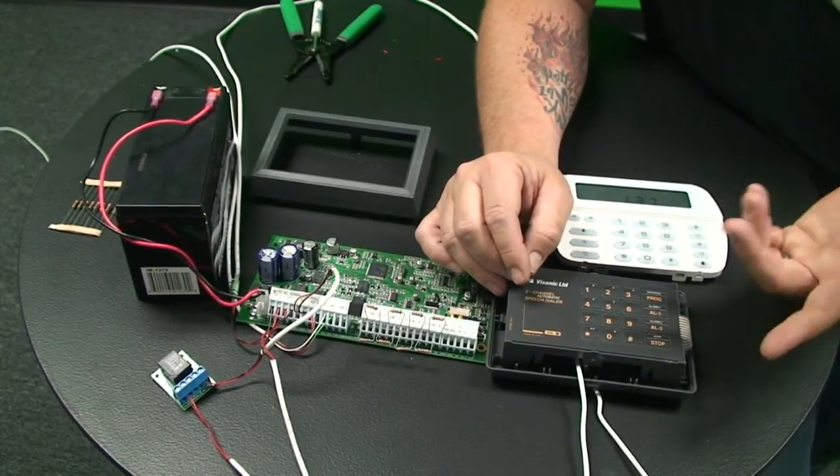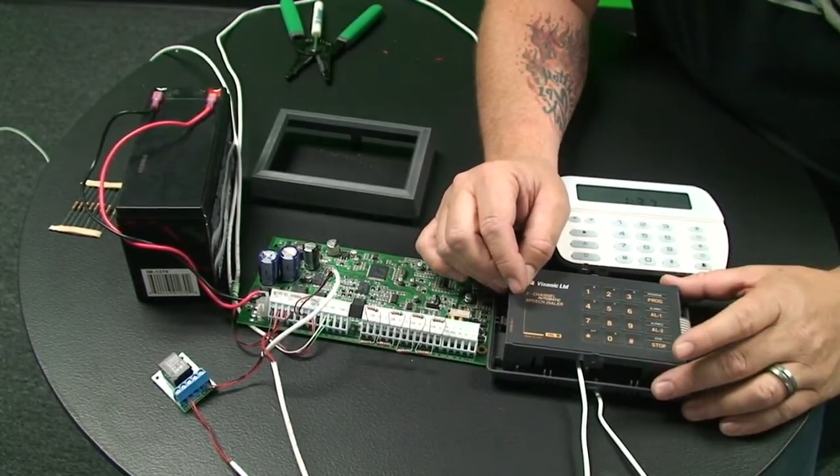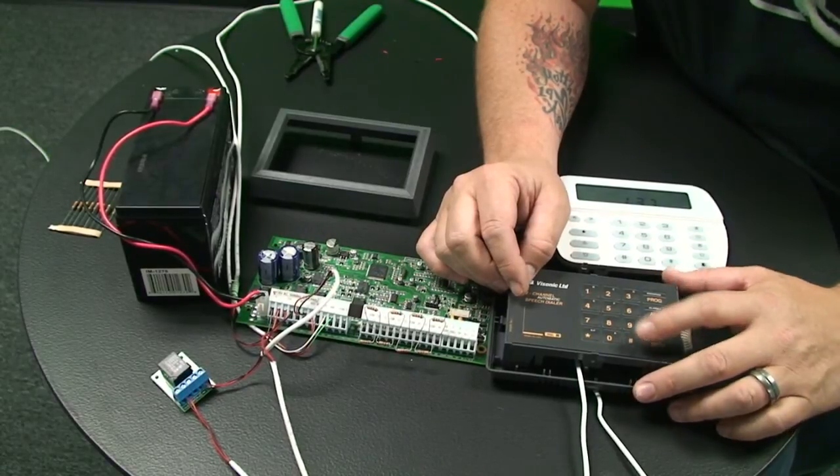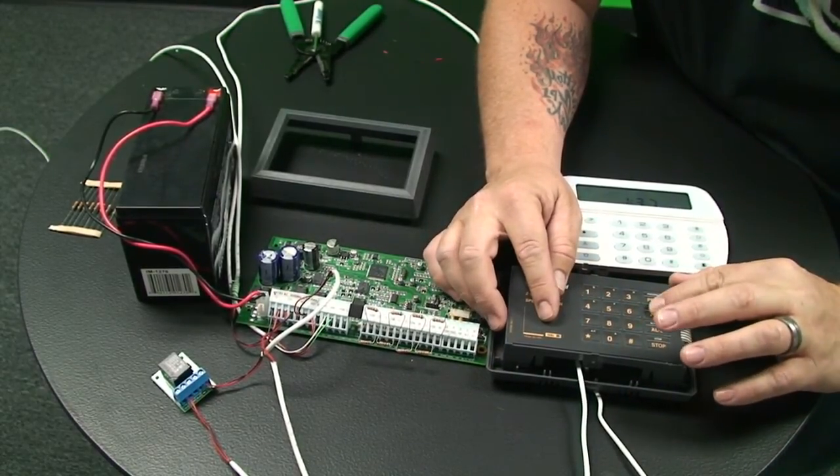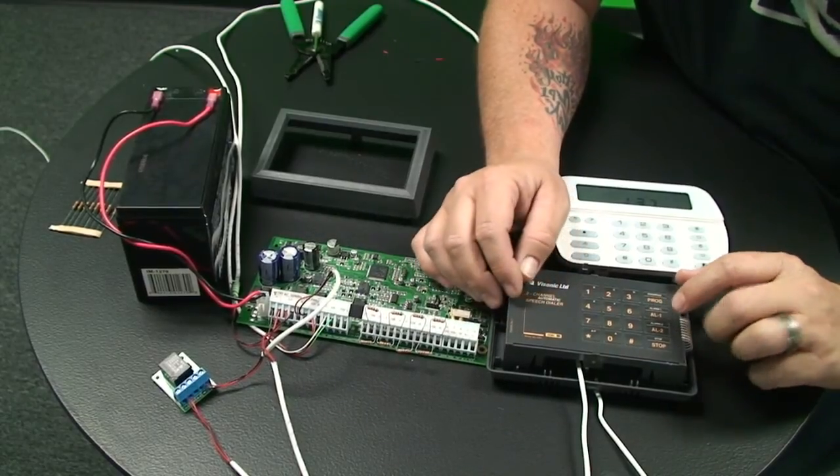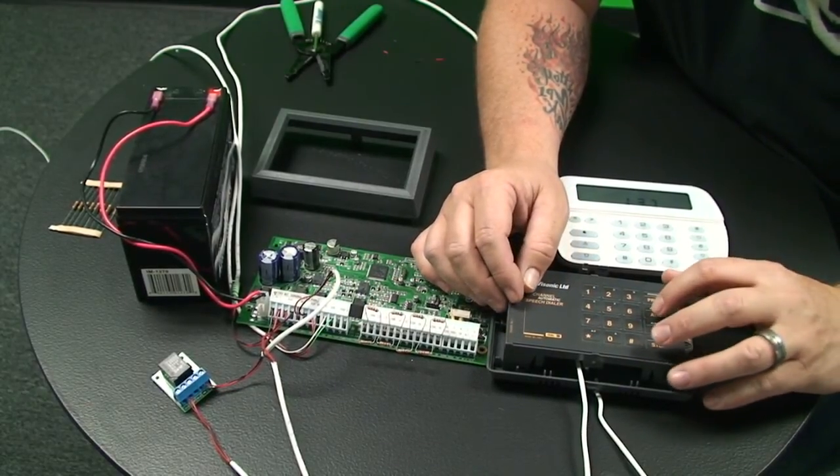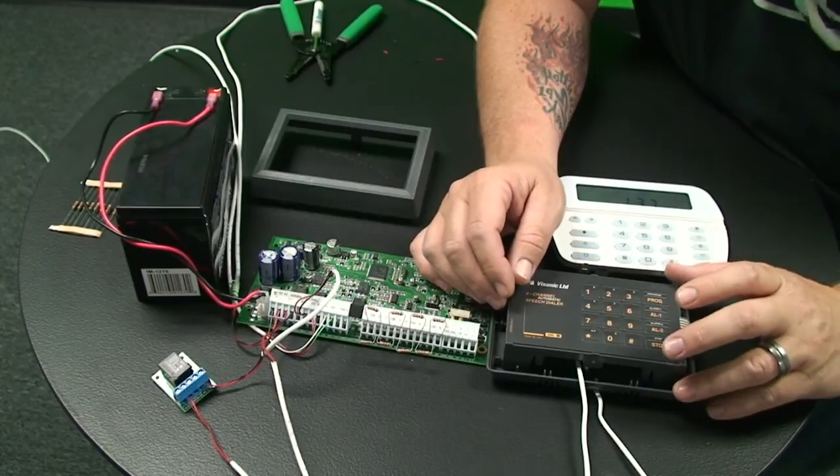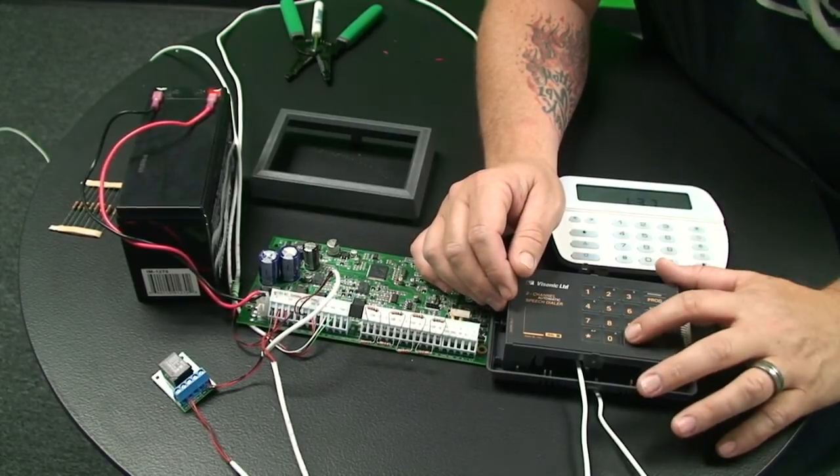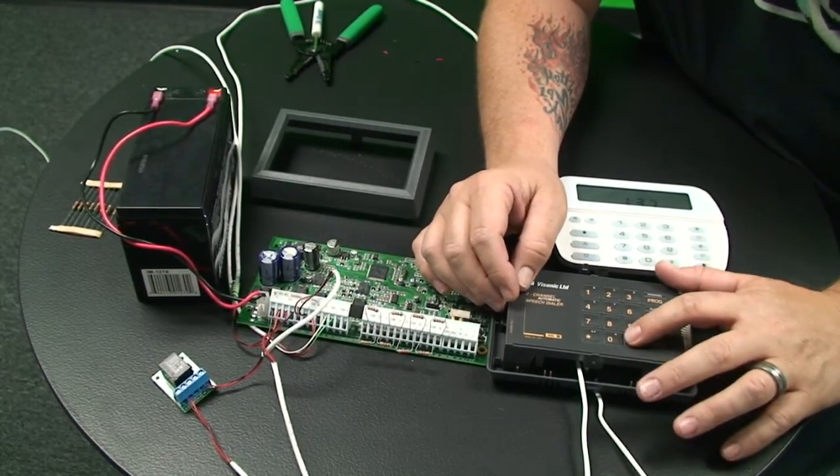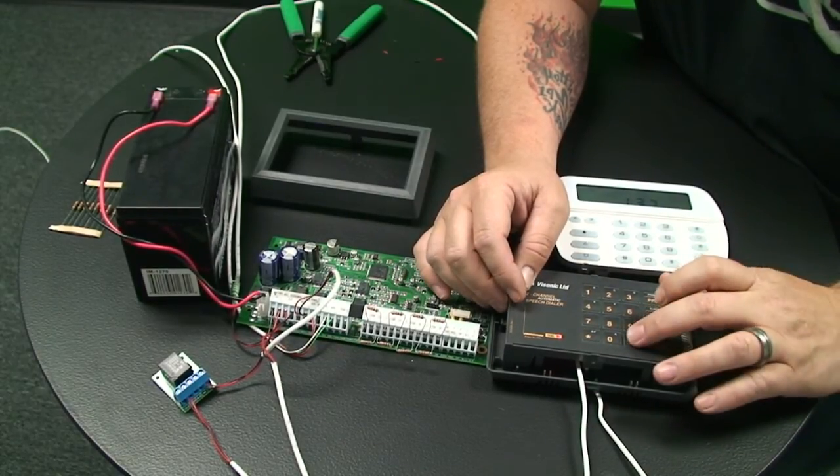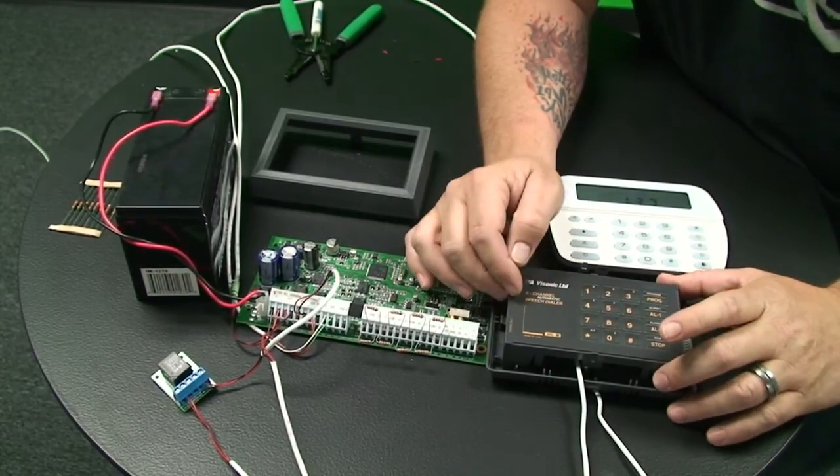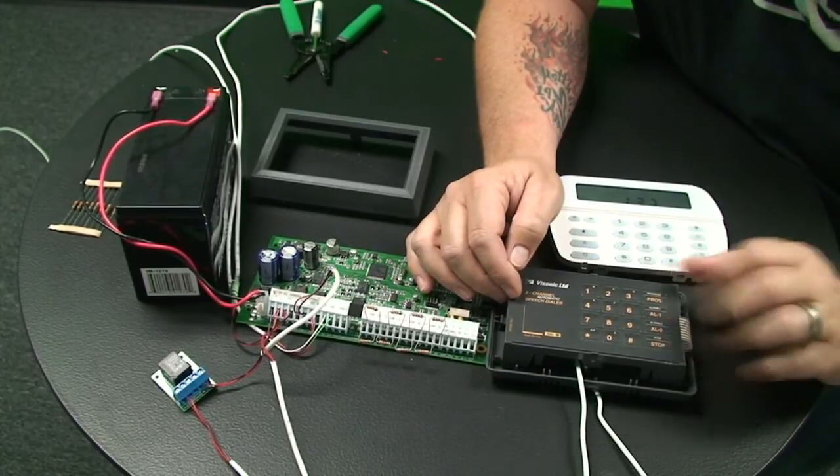So now we can actually program a message, and this is very simple to do. You can press the pound key, and then you'll see the dial light come on. Immediately press and hold down AL1. When you do that, you can actually deliver your message, and you have about 10 seconds to deliver a message. When you're done, you just press the pound key. So we go program, and we say my alarm is going off, and then press the pound key. Dial light extinguishes, and now you have a message for AL1.